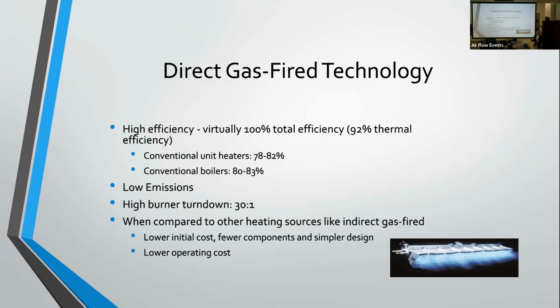Direct fired burners have very low emissions, which they have to be because you're putting those products of combustion into the airstream rather than venting them. Also, one of the big advantages, you've got a really high burner turn down with your direct fired burners. You're looking at 30 to 1, so you can get really precise temperature control. You don't have big temperature swings, and you're not overheating and then cycling a burner off. So you can achieve really good temperature control with your 30 to 1 burners.